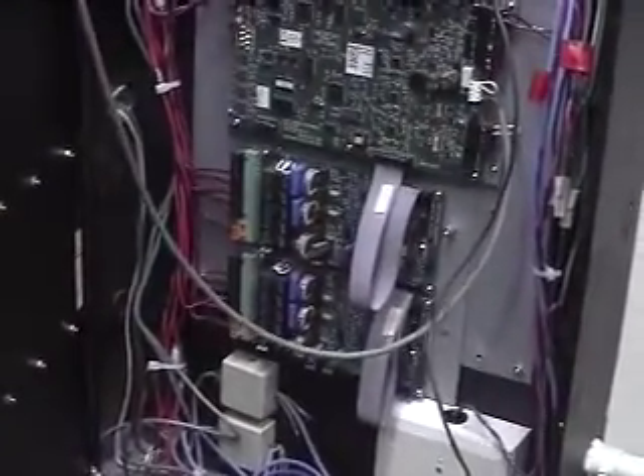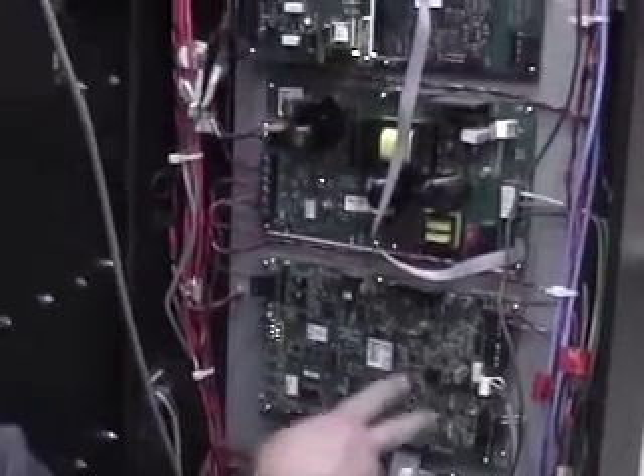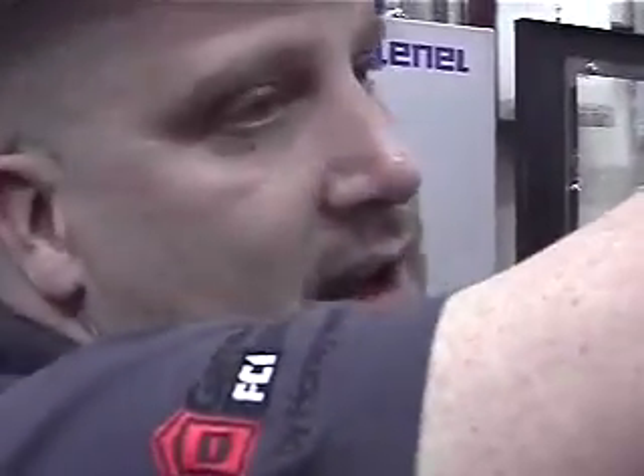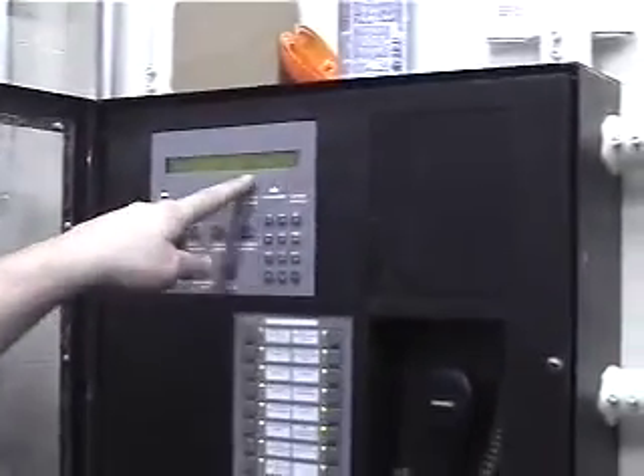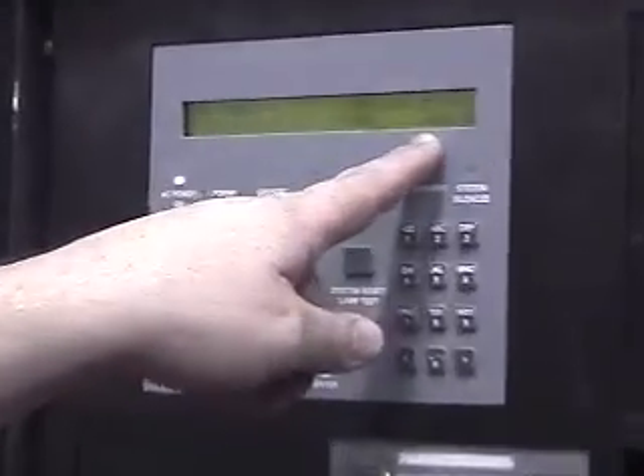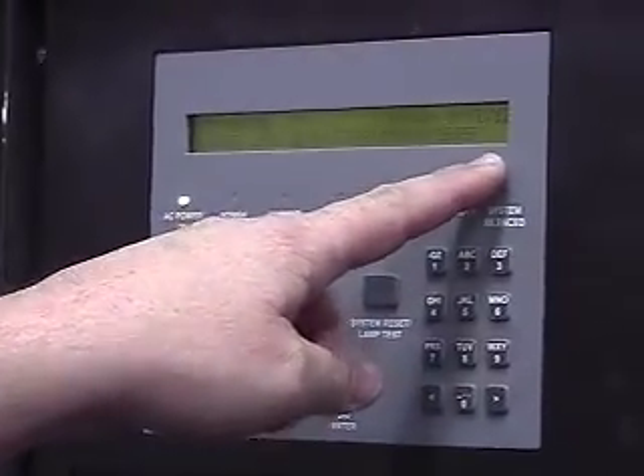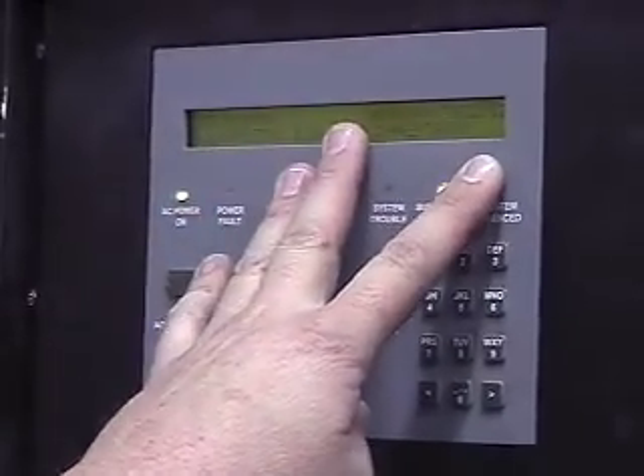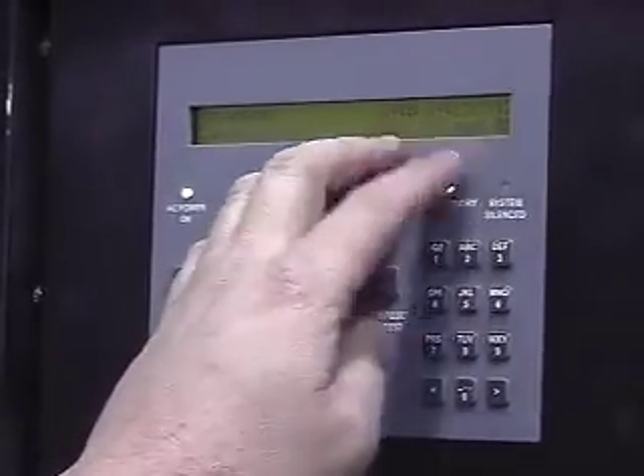So on this floor, we've got the speaker module and your amps. The upper floor has a voice panel, and the floor above that has a voice panel, and so that one's node 5, node 4, node 3. So when you look on here at the faults, you want to look at the node. Nodes 1 and 2 deal with your detector loops. Anything node 3 and above deals with your speaker faults and stuff, so your amp panels.